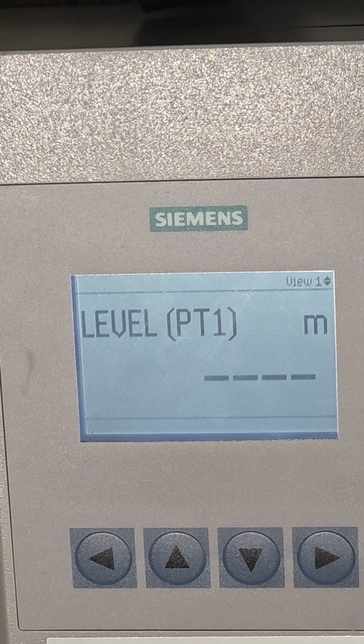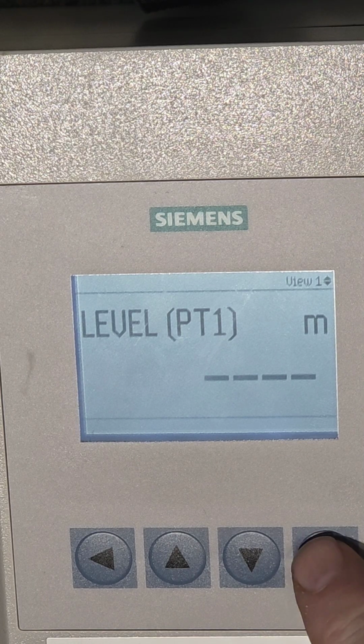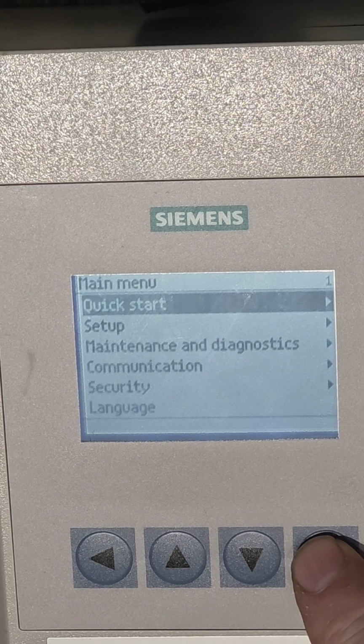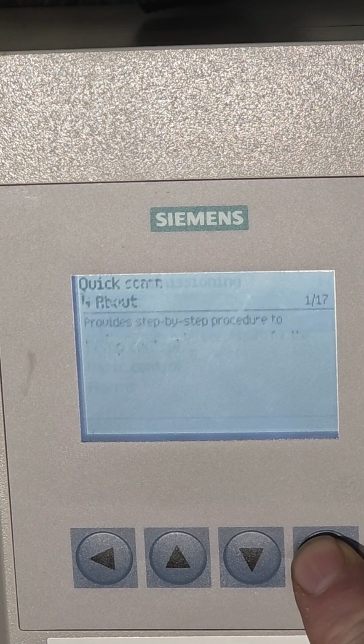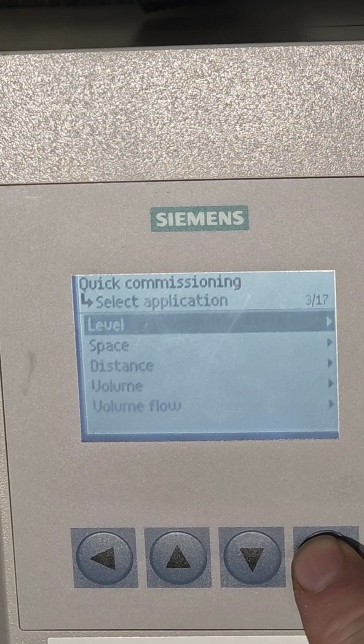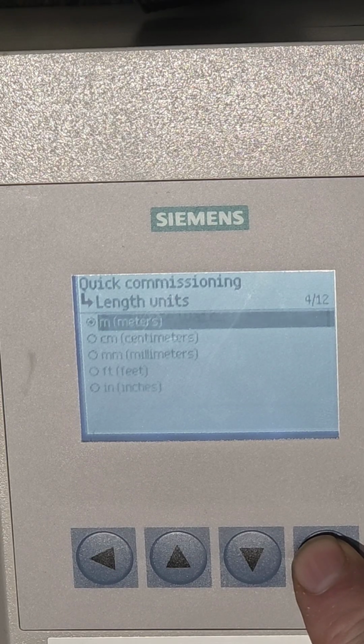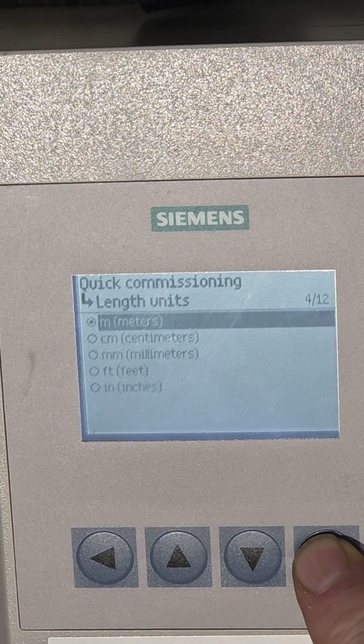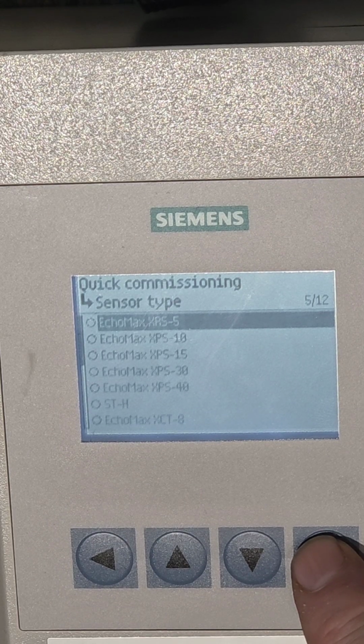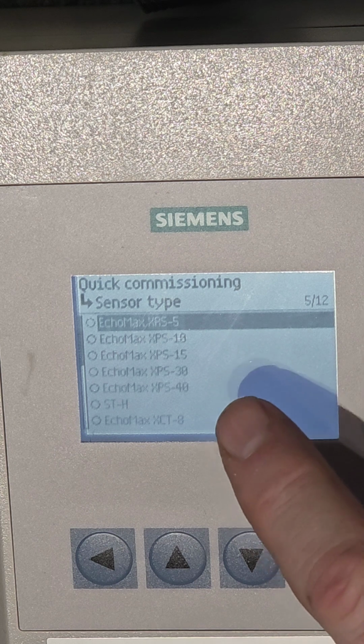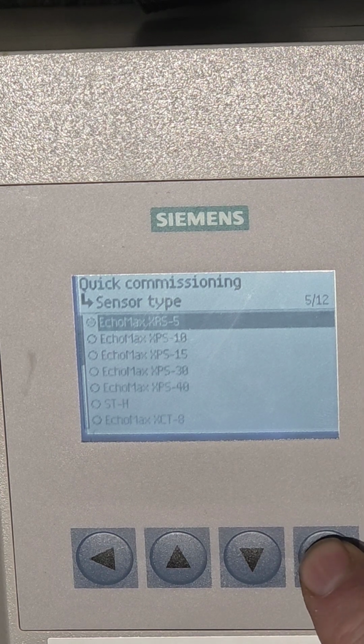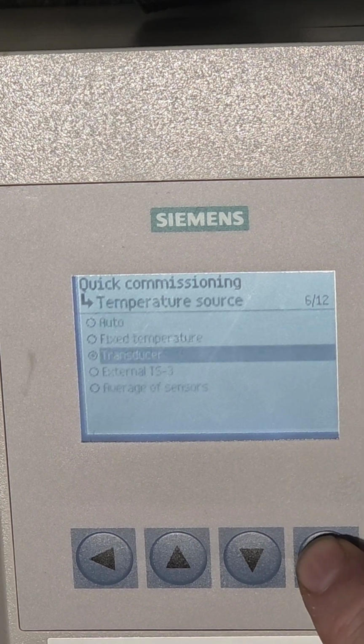I'm going to carry out a quick setup of two pumps on an LT500 Hydroranger. On the start, we press the right arrow key, quick start, quick commissioning, right arrow again, level. I want it to be meters, which it already is. I'm going to choose the ultrasonic head, in this case it's an XRS5. Highlight that one and right arrow again. Temperature is coming off the transducer.